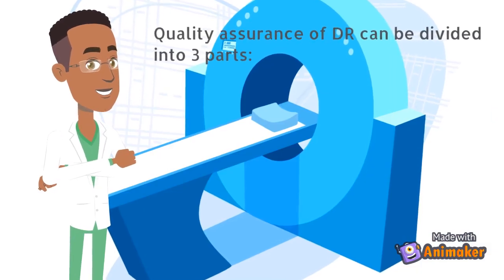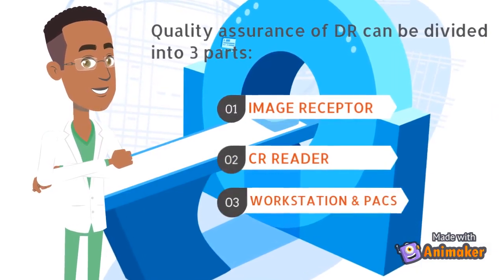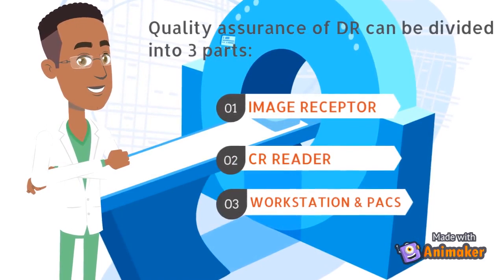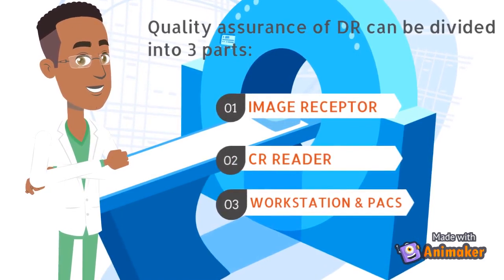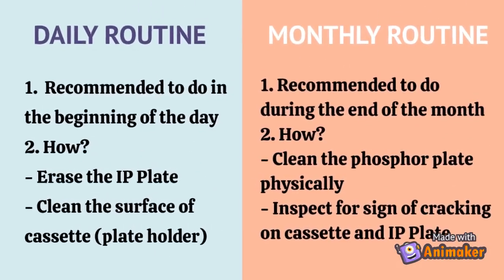Quality assurance of digital radiography can be divided into three parts: image receptor, CR reader, and the third part is workstation and PACS. The quality assurance can be conducted through a daily or monthly basis.